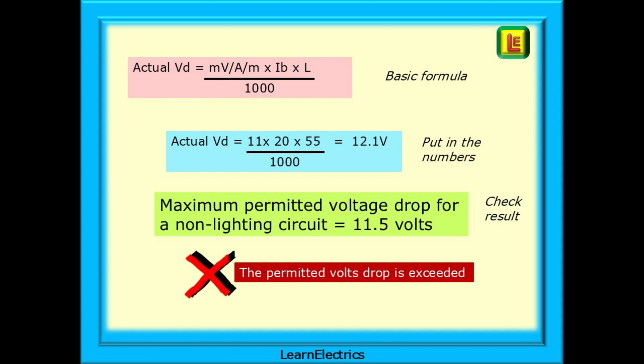So, start with the basic formula and put in the numbers that we have. 11 from the pink table, 20 amps from our earlier calculation, and 55 metres as suggested by the on-site guide. Dividing this by 1000, we have a voltage drop of 12.1 volts. When we check the result, we find that the voltage drop limit will be exceeded for this circuit if we use the full 55 metres. Too much voltage is lost in the cables. The maximum permitted voltage drop for a non-lighting circuit is 11.5 volts.